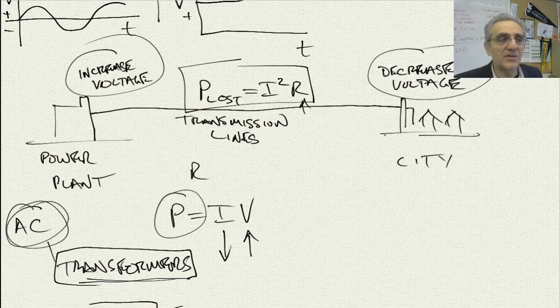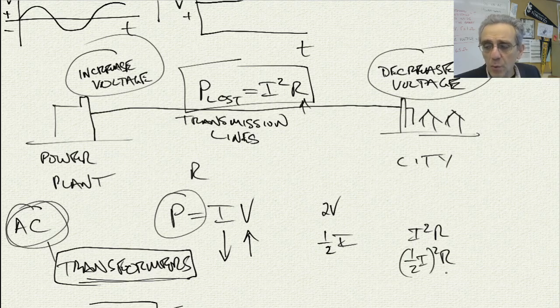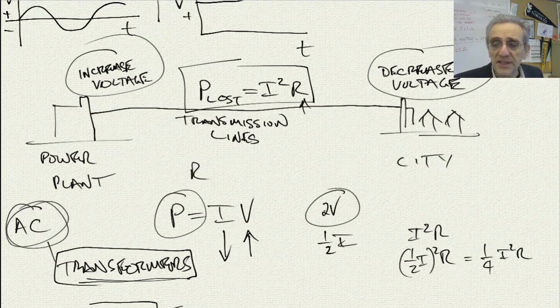And that's what allows efficient use of power transmission. Just to clarify, think about what happens if we double the voltage. If you double the voltage, then you have half the current. And if you have the current, what's the power loss? Well it's I squared R, but now it's one-half I squared R, which is essentially one-quarter I squared R. So if you double the voltage, you only lose a quarter of the power in the transmission.